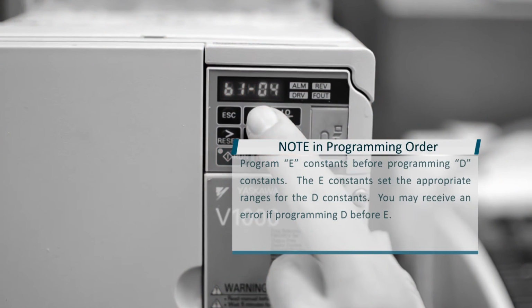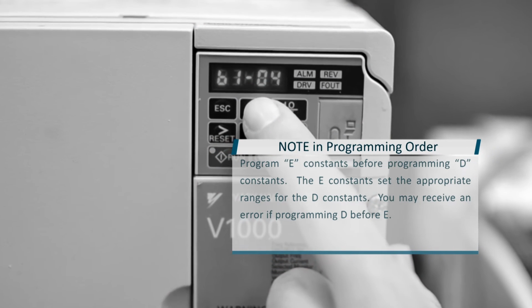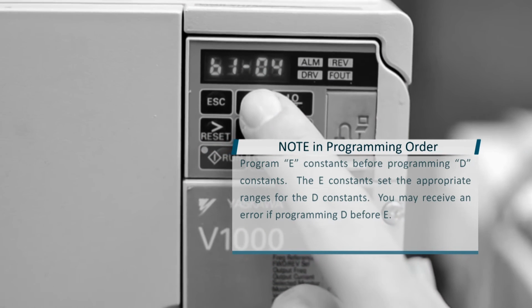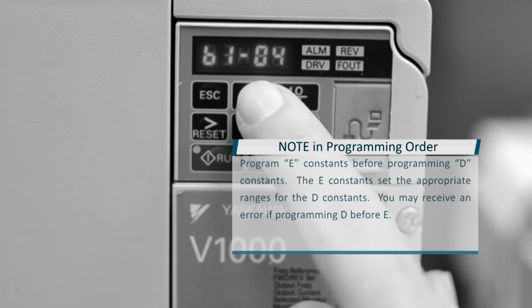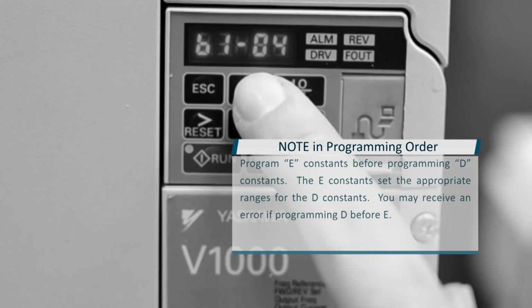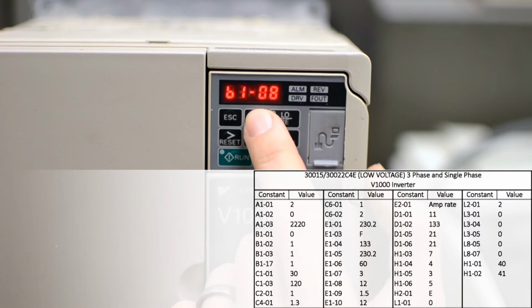Let's take a brief second to note programming order. We need to program the E constants before programming the D constants. The E constants set the appropriate ranges for the D constants. If you do not program E before D, you may receive an error during programming.